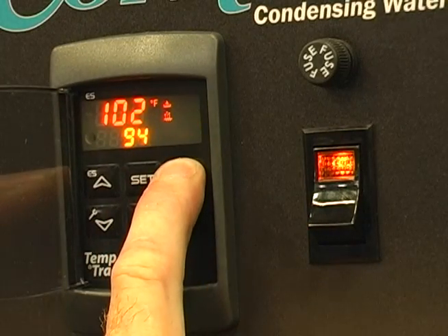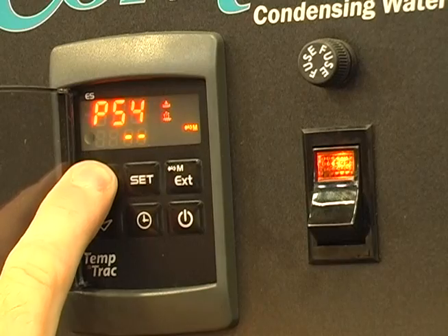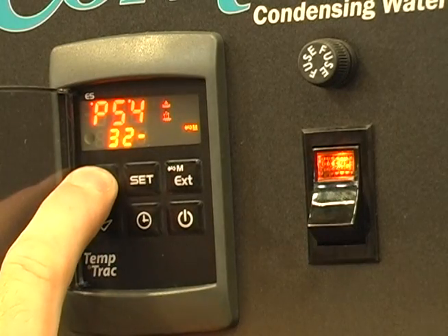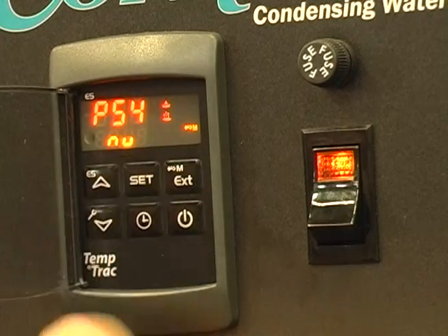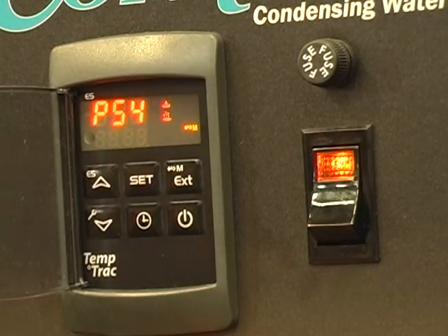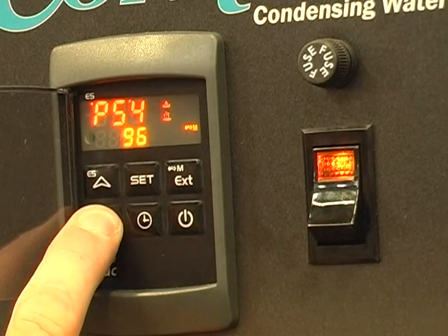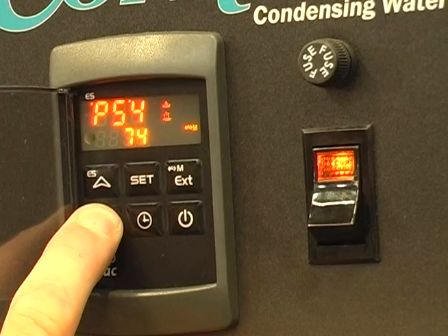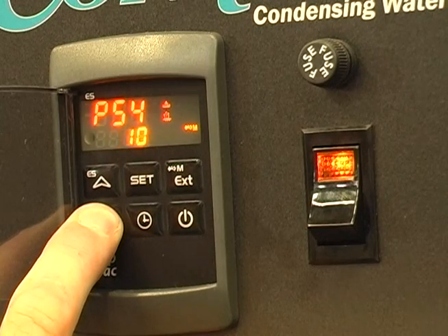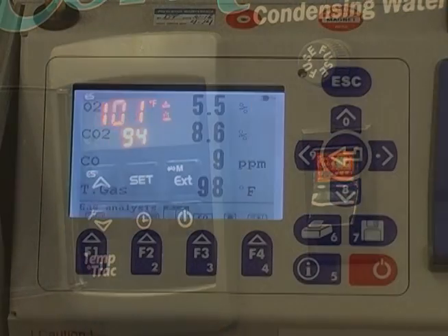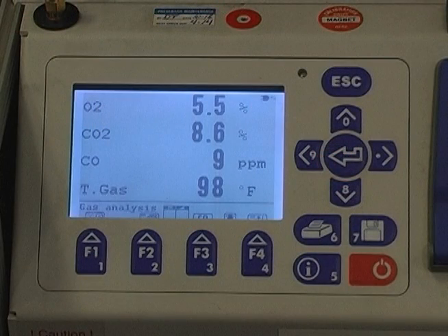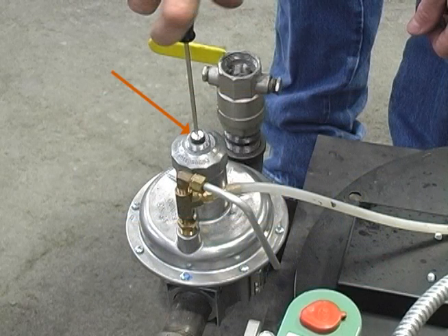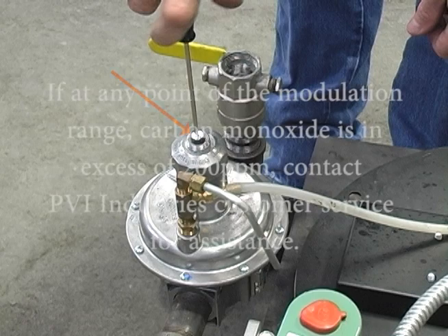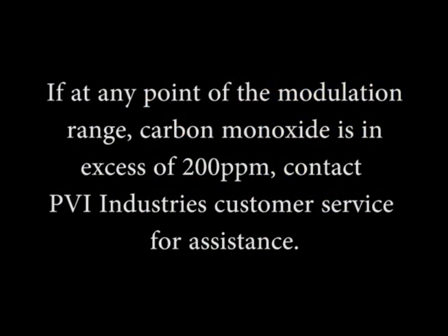Reset the modulation rate to low fire and confirm CO2 settings are still in the proper range. If needed, adjust CO2 by turning the regulator screw. If at any point of the modulation range carbon monoxide is in excess of 200 parts per million, contact PVI Industries customer service for assistance.